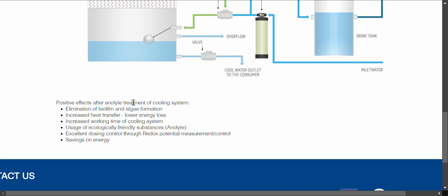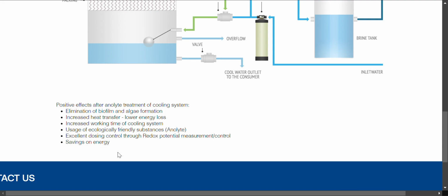The positive effects of using anolyte treatment in a cooling system: elimination of biofilm and algae, increased heat transfer, lower energy loss, increased working time of cooling system, use of ecologically friendly substances, excellent dosing control through redox potential measuring and control, and it saves dramatically on energy costs.